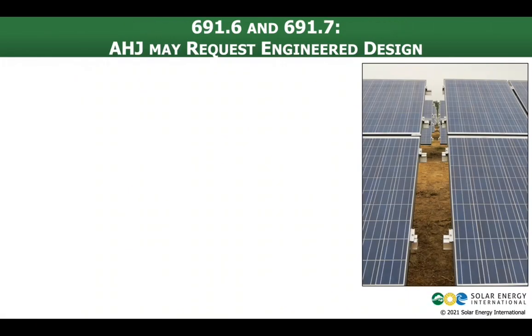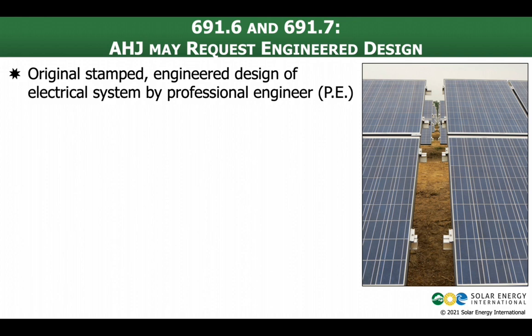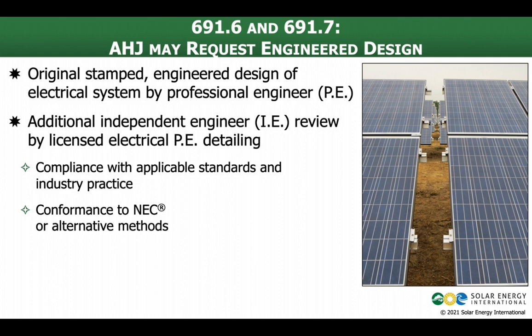Sections 691.6 and 691.7 talk about interaction with the authority having jurisdiction. I mentioned earlier that one of the purposes of Article 691 is to alleviate some of the burden on the AHJ, and this specifically goes into what they may request in terms of an engineered design, an original stamped design from a licensed professional engineer. Right? It's going to be engineered, it's going to have a stamp on it, and they're going to have to be licensed in the state where the system's installed, all that kind of stuff. Now, the AHJ may also request additional independent engineer review of this plan set. So a separate independent engineer, paid for by whoever's getting the permit here, is going to look at that plan set.